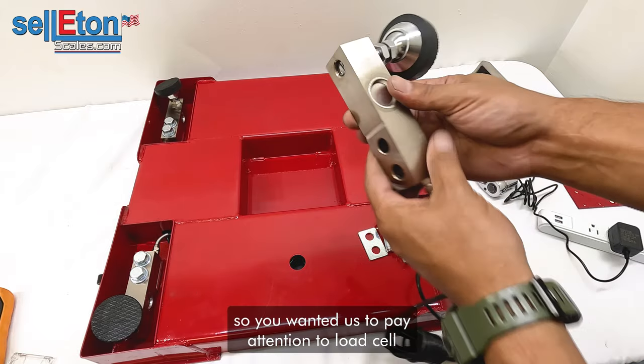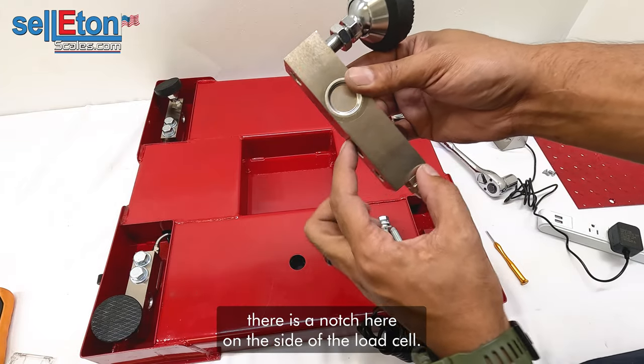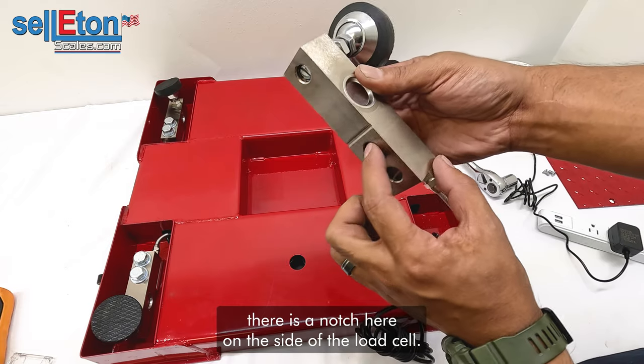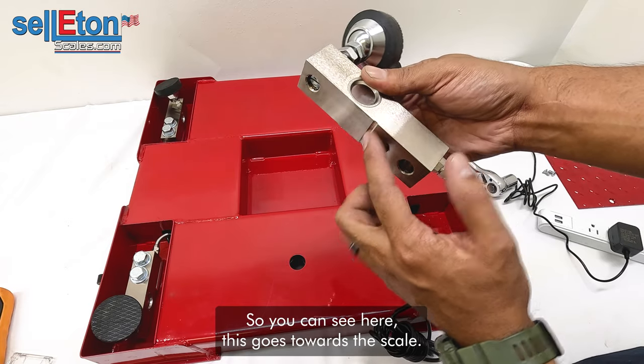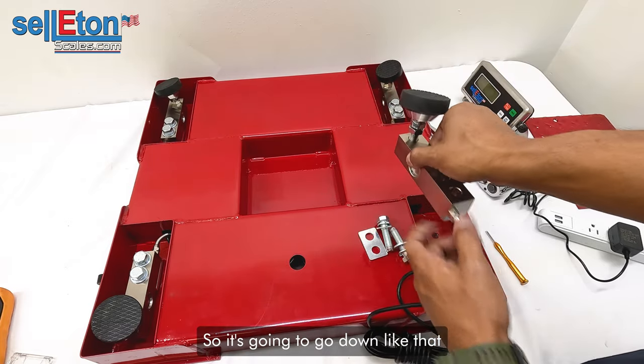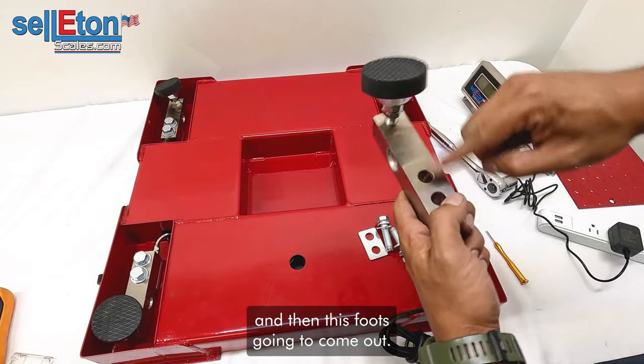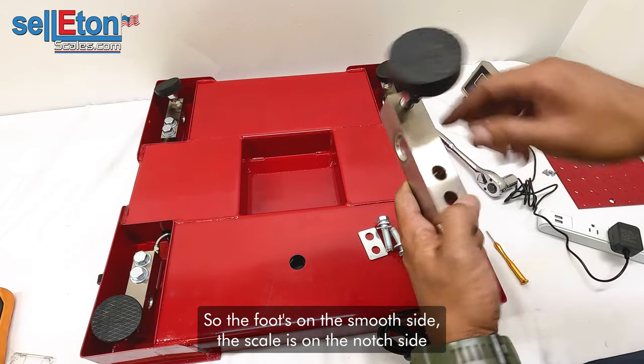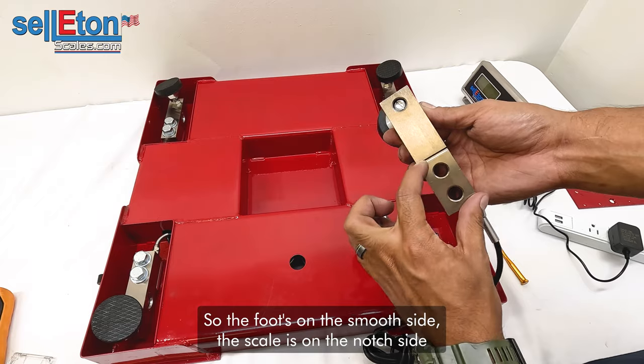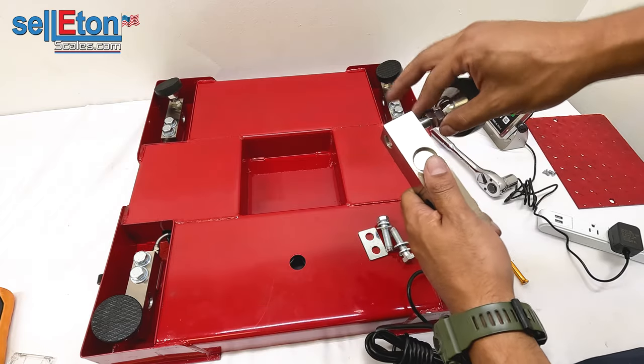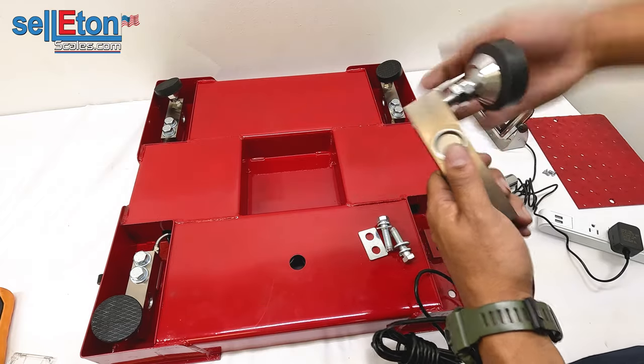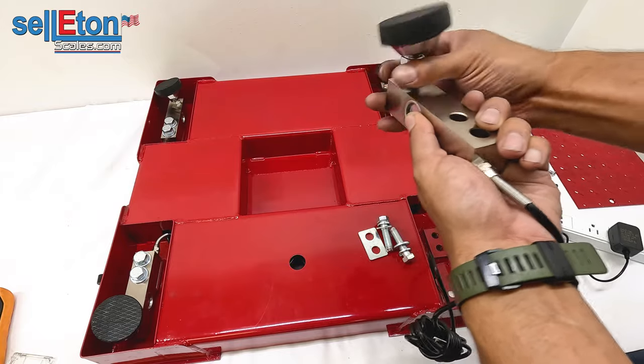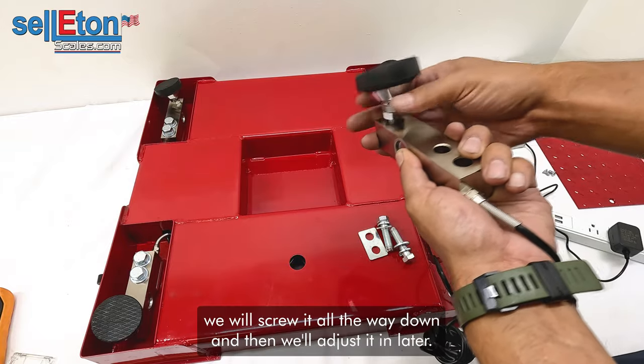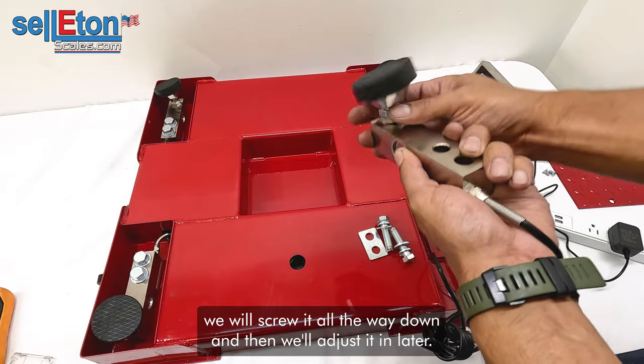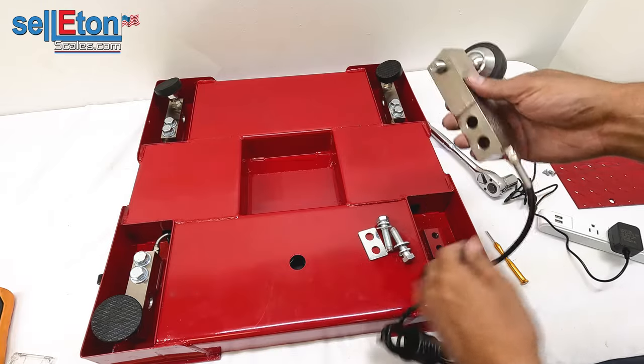So you wanna just pay attention to the load cell. There is a notch here on the side of the load cell, you can see here. This goes towards the scale, so it's gonna go down like that, and then this foot's gonna come out. So the foot's on the smooth side, the scale's on the notch side. Okay. I'm just going to screw it all the way down and then we'll adjust it in later.